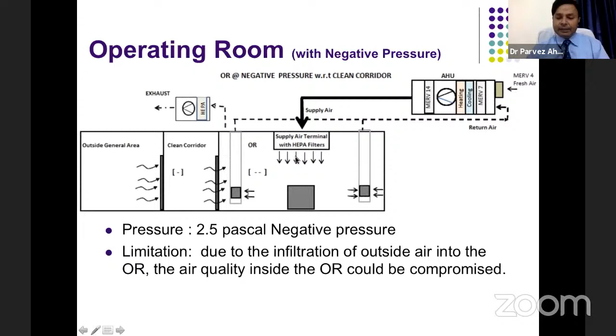The only limitation of this model is that due to infiltration of outside air into the operation room, the air quality inside could be compromised, because other aerobic organisms come inside and can harm the patient as well as the healthcare providers. That is how we can create a negative pressure operating room.